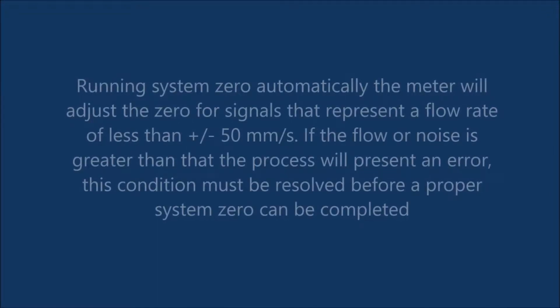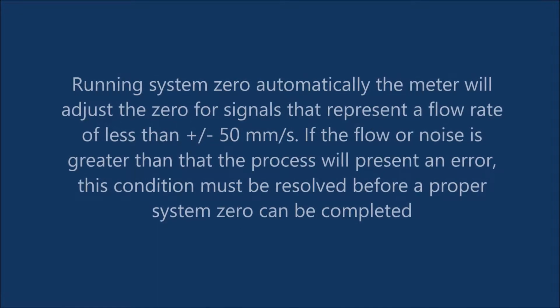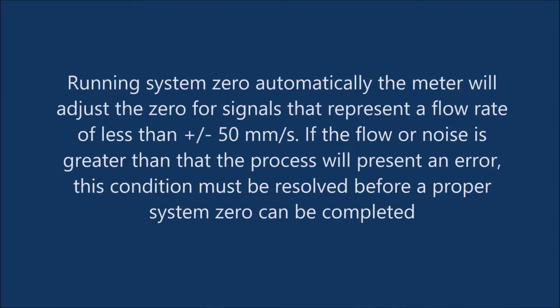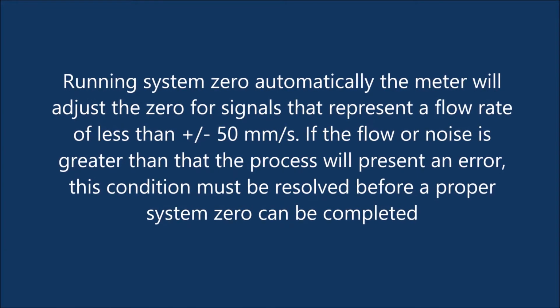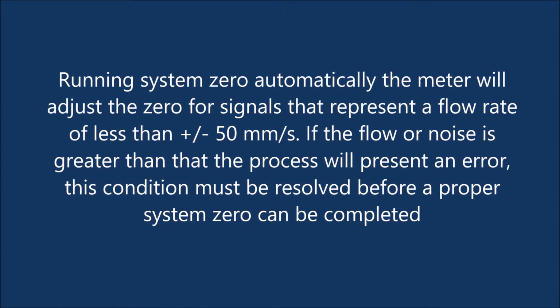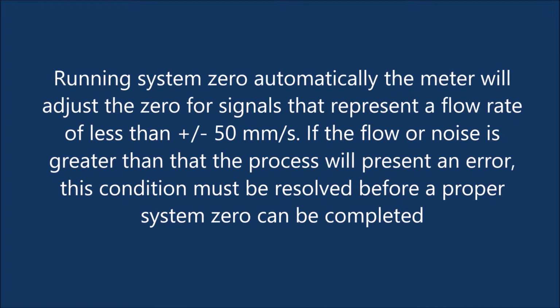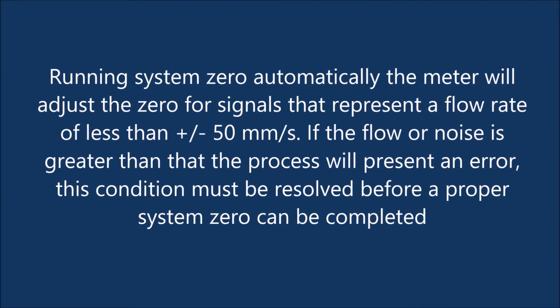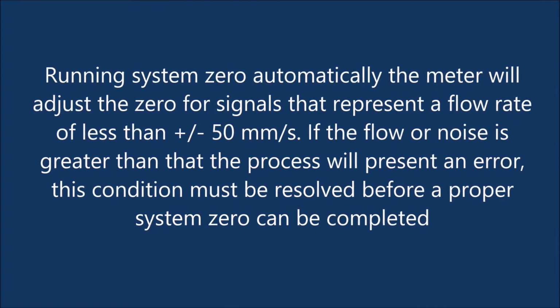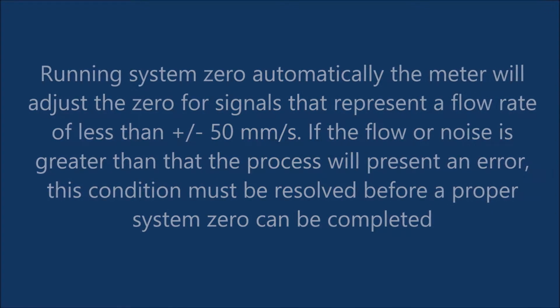Running system zero automatically, the meter will adjust the 0 for signals that represent a flow rate of less than plus or minus 50 mm per second. If the flow or noise is greater than that, the process will present an error. This condition must be resolved before a proper system zero can be completed.